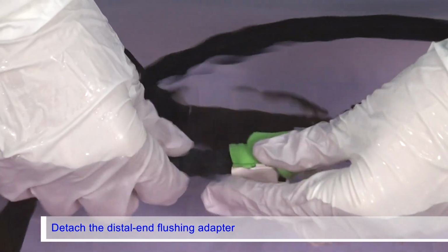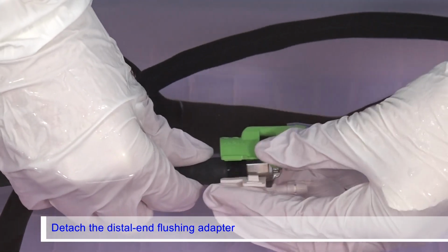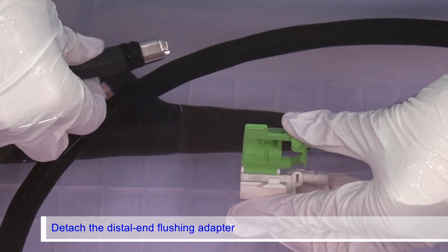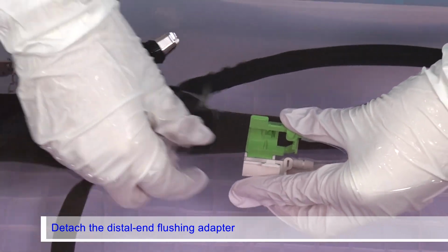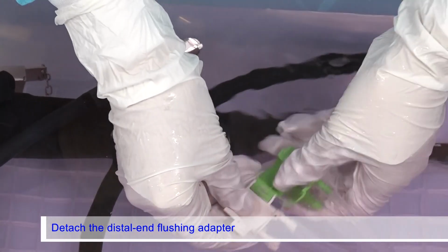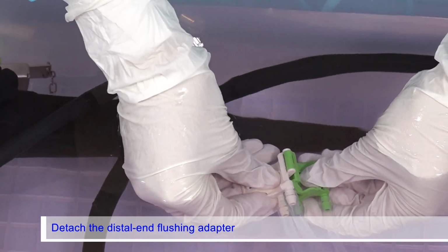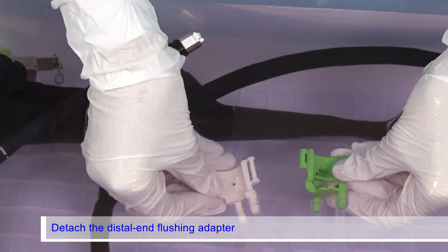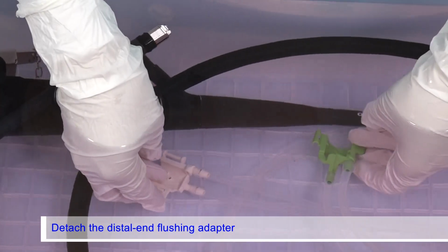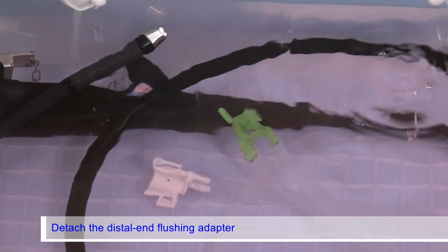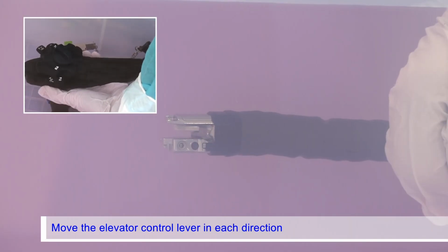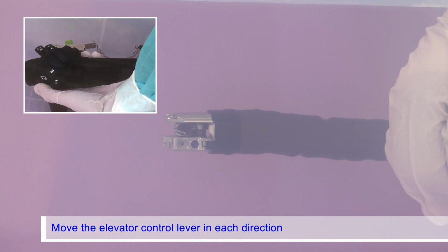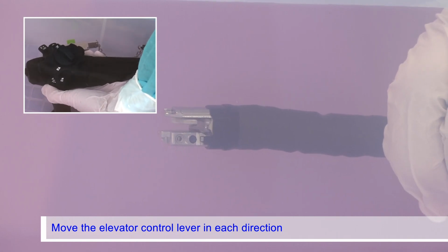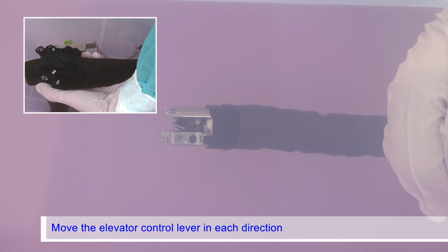While immersing the endoscope and the distal end flushing adapter completely in the disinfectant solution, open the white cover and the green cover to detach the distal end flushing adapter from the endoscope. Then, separate the white cover and the green cover. While immersing the endoscope completely in the disinfectant solution, move the elevator control lever in each direction 3 times.